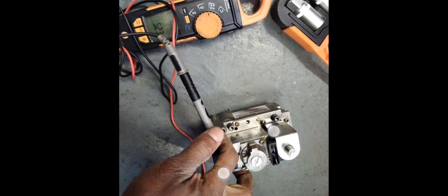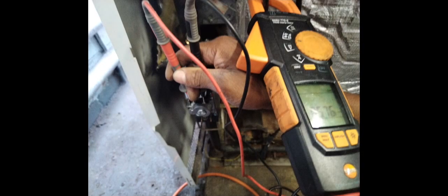But whilst carrying out checks on this gas valve, I did resistance checks to see the existing gas valve and the new gas valve to see the difference of the resistance. As you can see here, so this is the old gas valve. I had 0.591, so I checked out my other test point on the gas valve and I had 5.23. And then I checked on my new gas valve and I had 0.575, 0.576 rather, and then at my other test point I had 5.01. So there wasn't really a big difference in the resistance. I think the existing gas valve was fine. I just think that the washers needed changing rather than the whole gas valve for the sake of the gas leak.